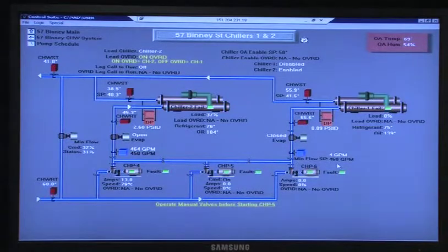Now the problem we were having with this is that originally, well, what we do now is when we start any chiller, we put the minimum flow valve to 80% open. So we're flowing all the water through the chiller, and then after a period of 20 minutes, it releases the valve and it comes up under flow. That ensures proper flow to the chiller, enough to make all of the flow switches across the bundles of the chiller. We do the same thing with the chilled water pump associated with that chiller.